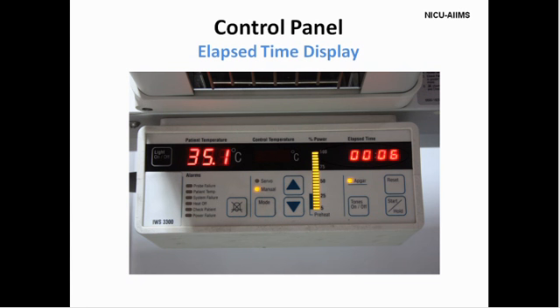In some warmers, there is an option of an elapsed time display. The elapsed time display indicates the elapsed time in minutes and seconds up to a maximum of 60 minutes. Press the start or the hold touch switch to activate this timer. You can also press the APGAR tones on and off to switch on the APGAR tones. This function helps in counting the heart rate, the respiratory rate, and for scoring of the APGAR scores.